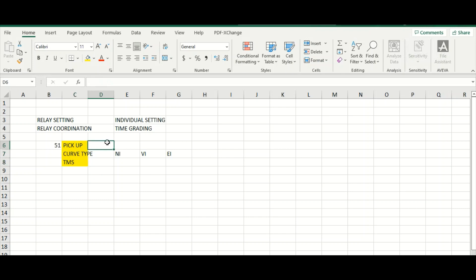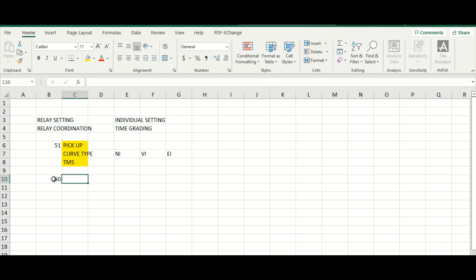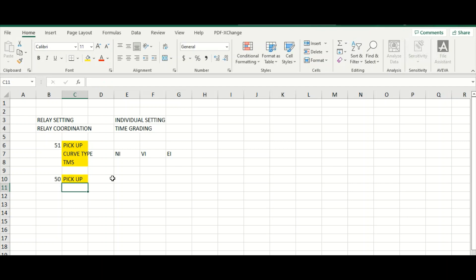This is phase overcurrent and IDMT relay. And what is required for 50 element? That means phase instantaneous. Here we need to specify relay pickup, and please note that curve type is not applicable for instantaneous function. This curve type is applicable for 51. This curve type is not applicable for 50.